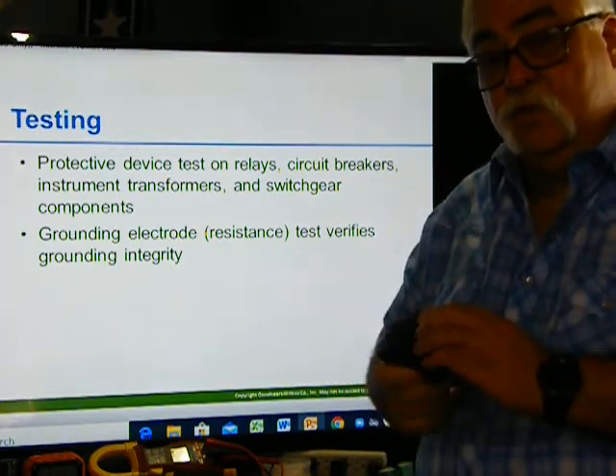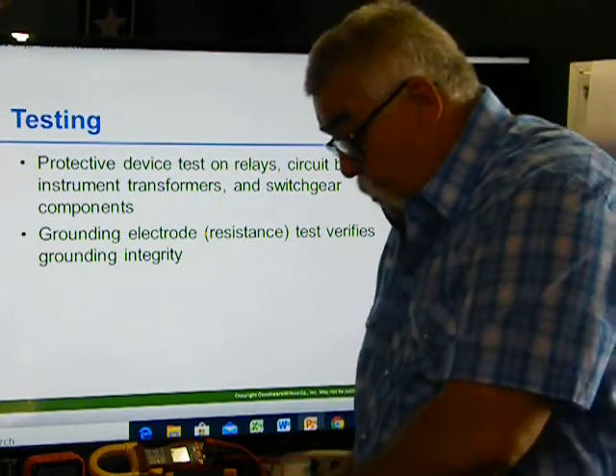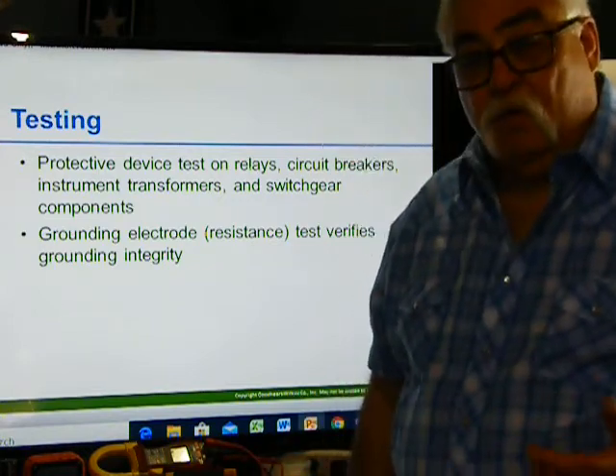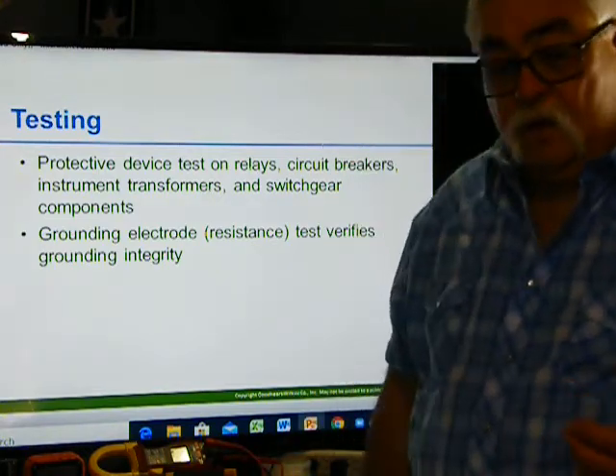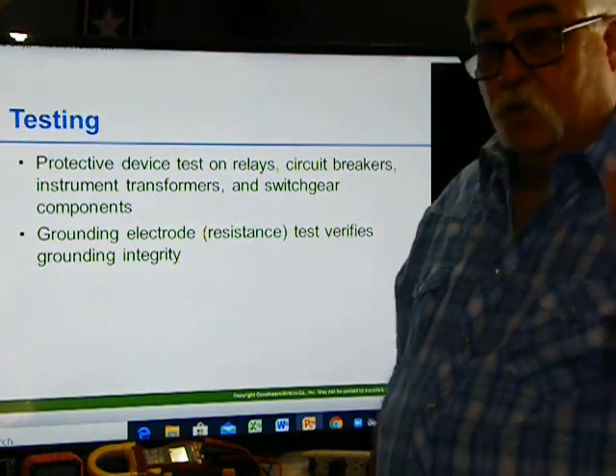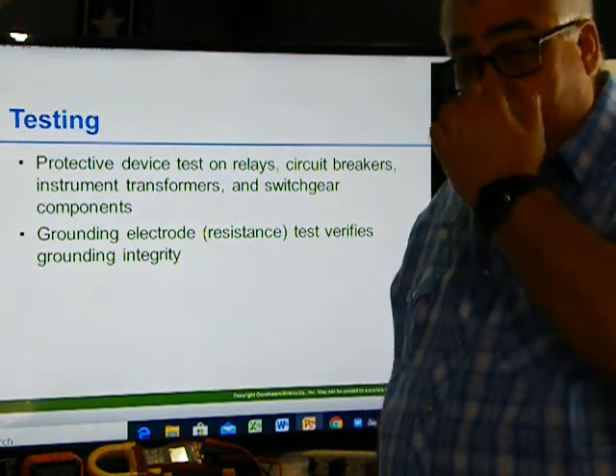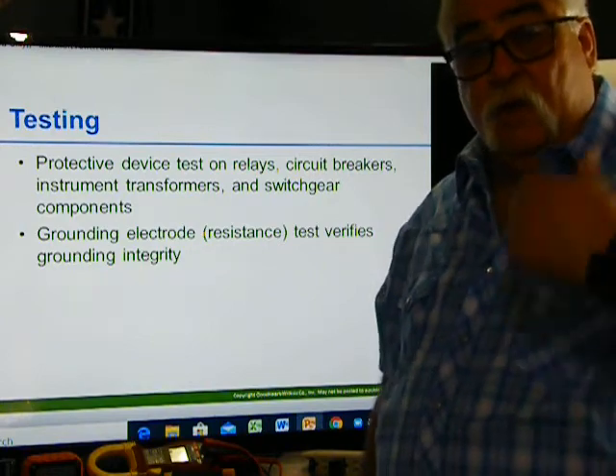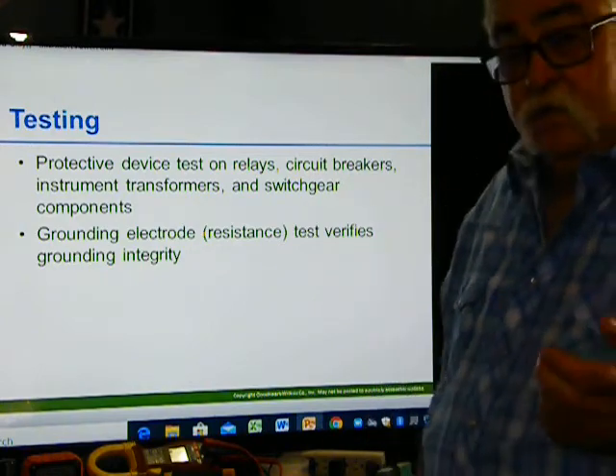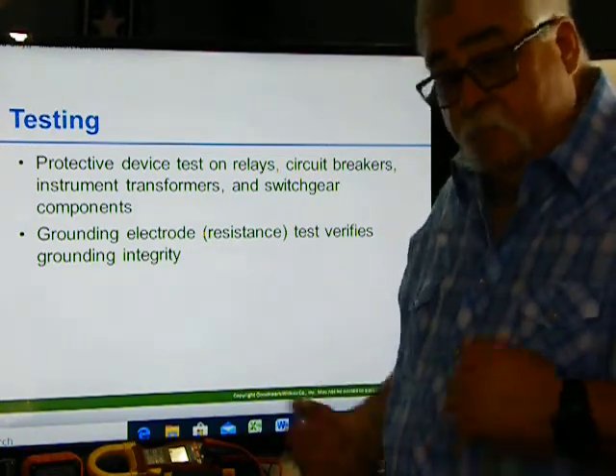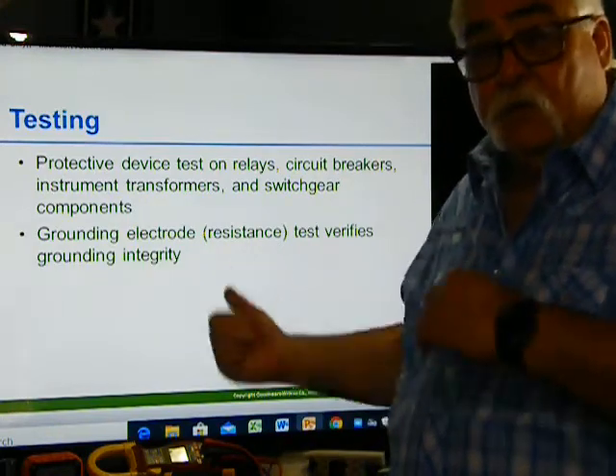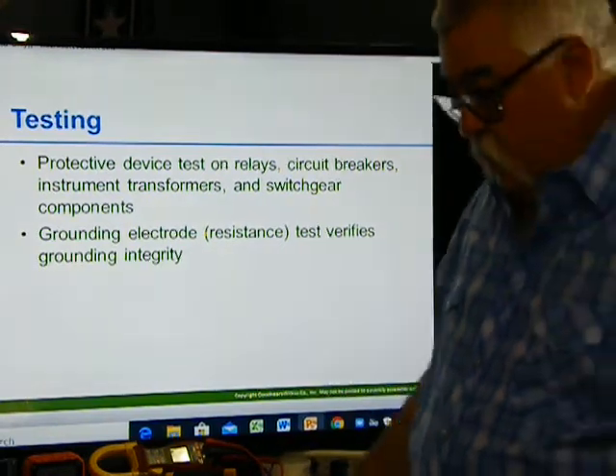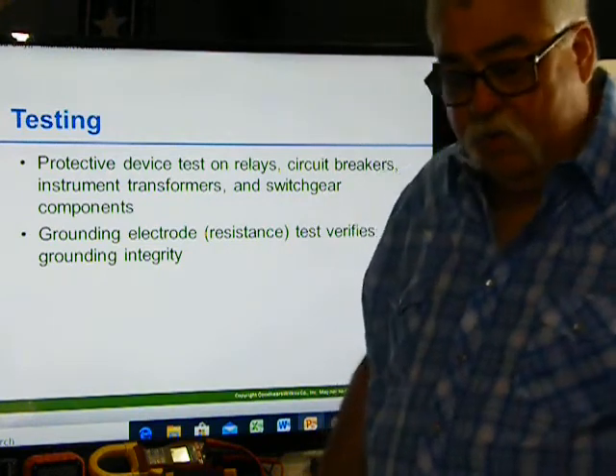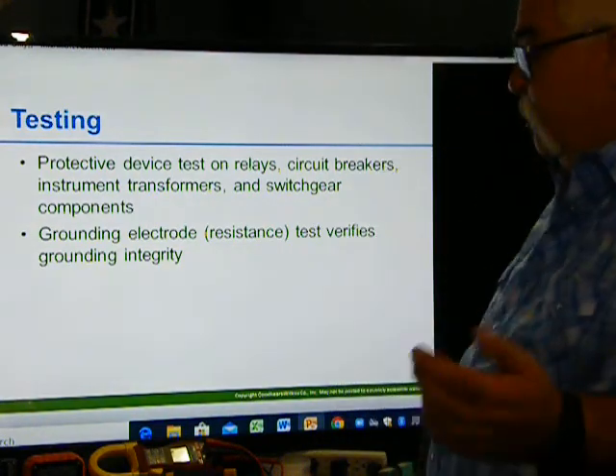So that's why we used to do that on the big air breakers, because you know we're talking about a 1600 amp, 1200 amp, 800 amp breaker that's controlling part of a building. So that breaker trips, you want to make sure that it resets again. If it doesn't do it, we took it out. We always had a spare. Put the spare in, then set that one out to get tested and remanufactured, re-certified, and whatever else they did.